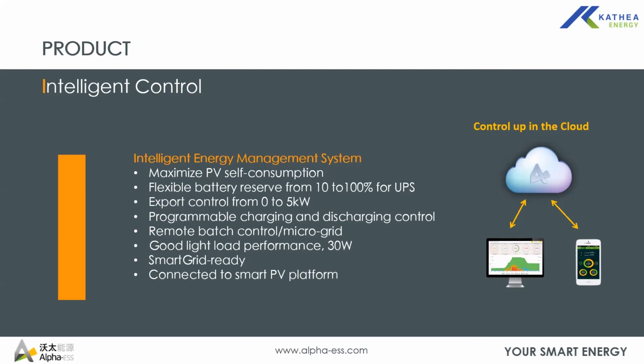The system is connected to a smart PV platform. I'll also show you that as well. It's quite a good platform with good aesthetics, so you can actually view your plant performance from PV production, load consumption, feed in, and you can see the fault log remotely, and actually change some of the settings, except for safety settings, which is the grid code. You can only do that when on the unit physically.